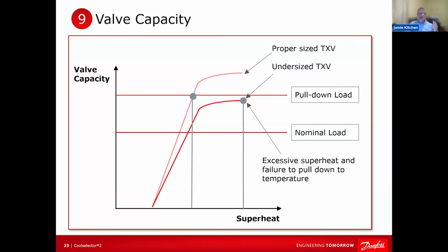Yeah, absolutely. So the same with a TXV. If you have a normal load and it's not too high, that undersized TXV, it might do okay. You might see slightly longer pull downs, maybe slightly higher superheat, but nobody knows what the superheat's supposed to be anyways half the time, so it doesn't matter. However, if you put product in there that taxes the load, in other words, it increases your load, now you're going to have a problem. You're not going to be able to pull that down. It's going to run forever. You're not going to meet pull down. And if you happen to be in a food scenario where you're data logging the temperature of the product, now you're going to have alarms everywhere, right? And now you're going to be in a problem because that product has stayed warm for too long, and it no longer has any value, right?